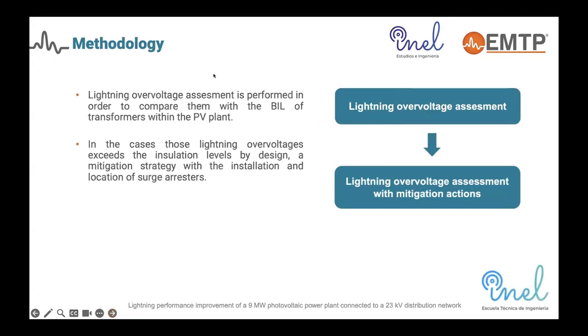The general methodology is based mainly on first performing the assessment and looking at the actual indicators — the actual overvoltages and number of back-flashover rates — then implementing or proposing which mitigation actions to move forward with. There are plenty of options to improve the performance of transmission and distribution lines and also those associated with the photovoltaic power plant. In this case, we decided to go with surge arresters.